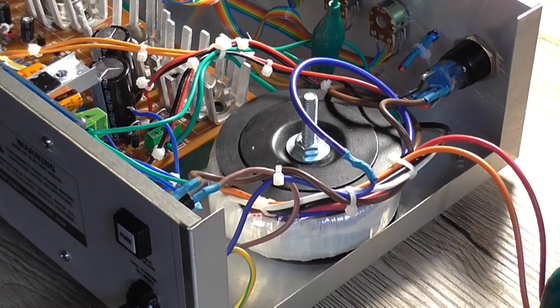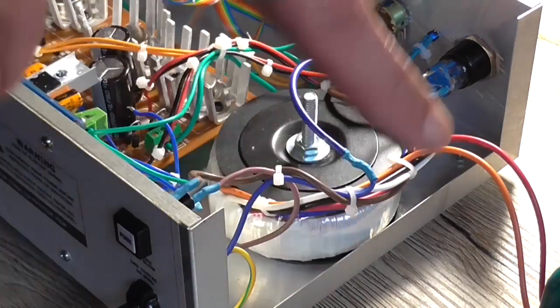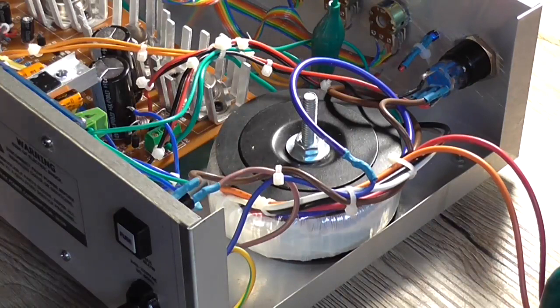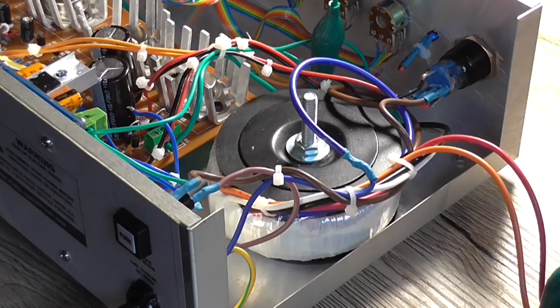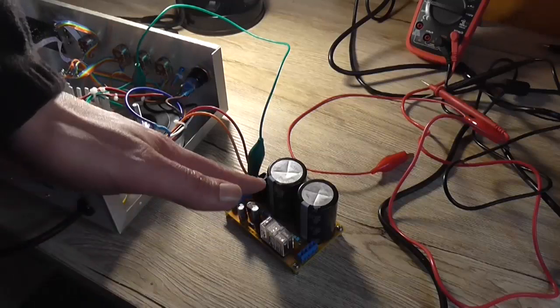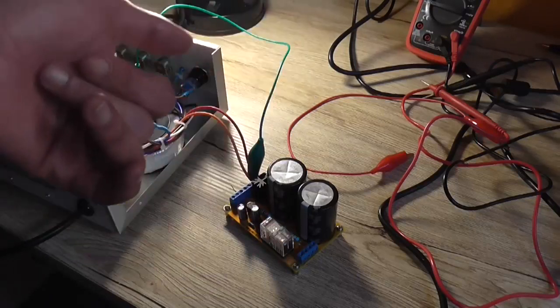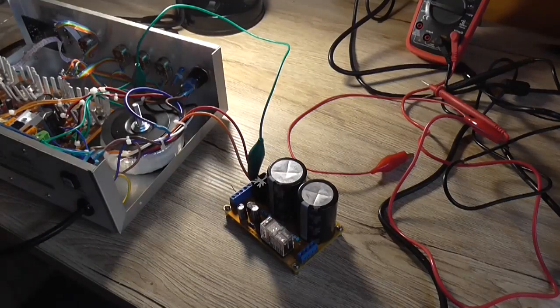This is only a 52V transformer, I can't remember offhand what VA rating that is, it should be written somewhere on the transformer. We've got 1.4 amp per winding, so this transformer is slightly underrated for this Class A project. I'd need at least a 160 VA transformer with roughly 3.2 amps of current per winding. So powering it anywhere close to full power on the amplifiers would probably be disastrous for the transformer, just saying.